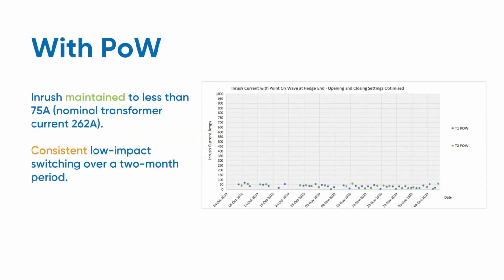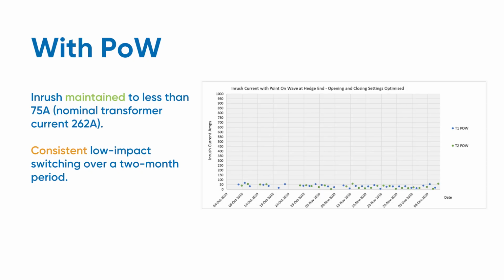Hopefully you can see this graph, a bit small. This is a graph from October to December when the system was commissioned and in service. The green is one of the transformers, the blue is the other. Effectively, they just took it in turns, and one day switched one off, the other day they switched the other one off. And this is the peak inrush current that was seen for every energization. These were nominal 15 MVA transformers with 262 amps per unit rated current. The inrush was maintained every single energization for a period of 2 months to less than 75 amps.